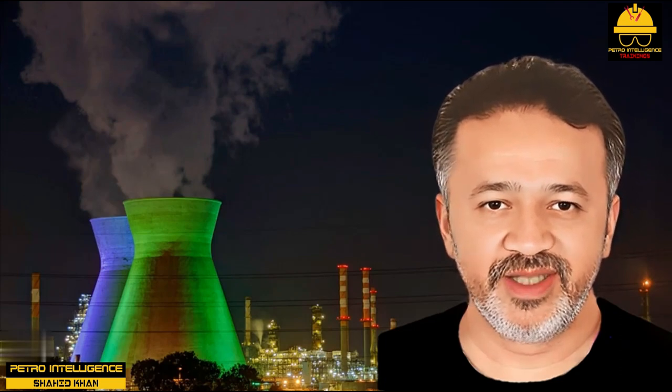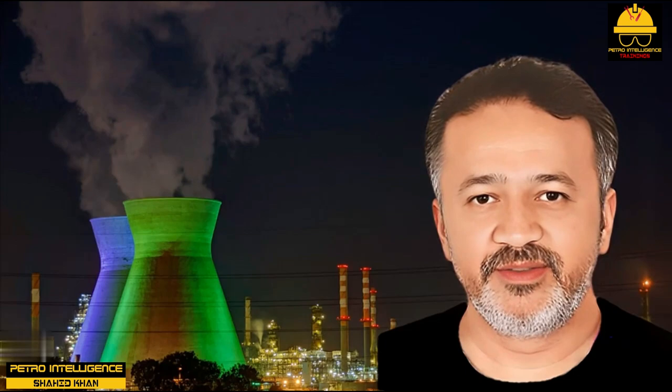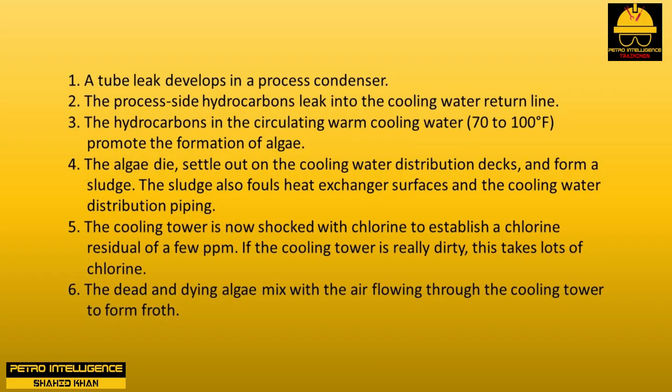Perhaps you have driven past a refinery cooling tower with frothy white foam billowing from its top. That's caused by the following sequence of events: one, a tube leak develops in a process condenser; two, the process side hydrocarbons leak into the cooling water return line; three, the hydrocarbons in the circulating warm cooling water (70 to 100°F) promote the formation of algae; four, the algae die, settle out on the cooling water distribution decks, and form a sludge.